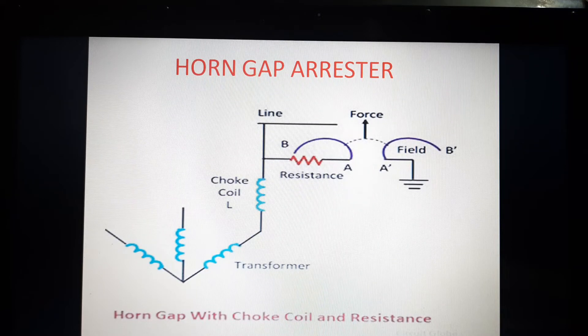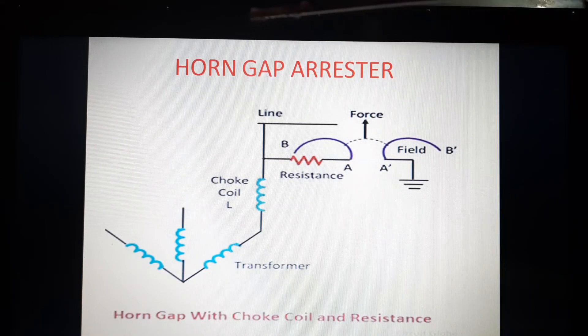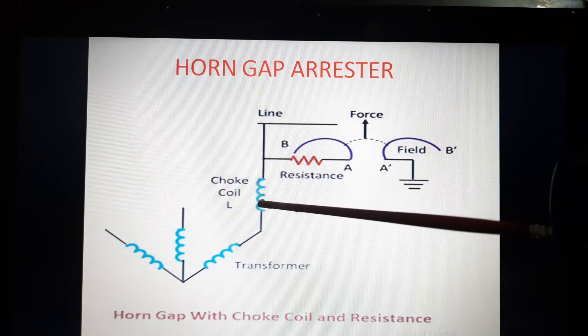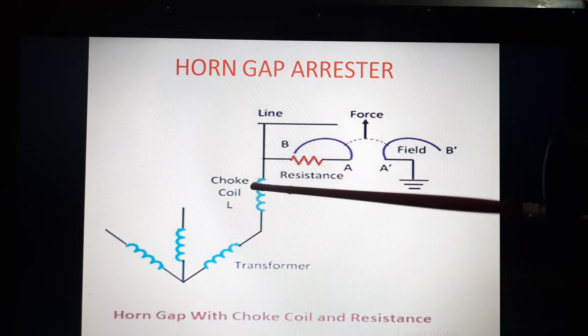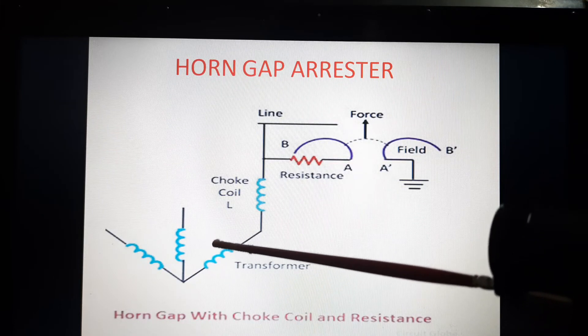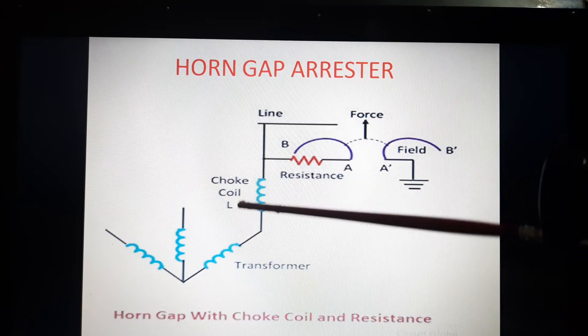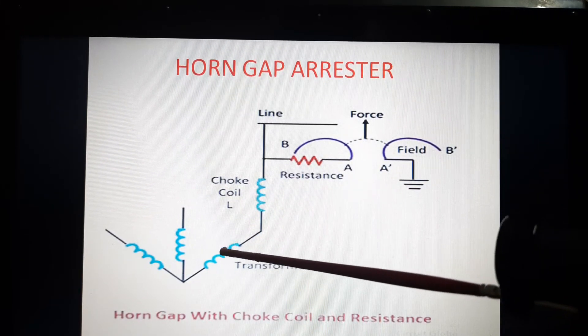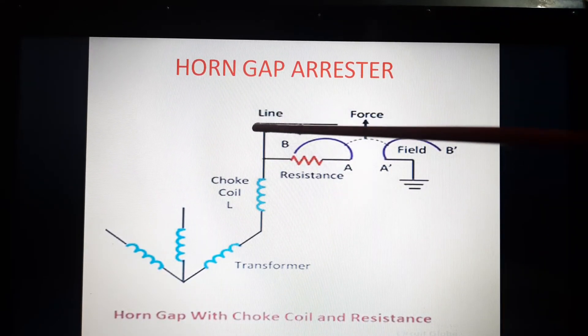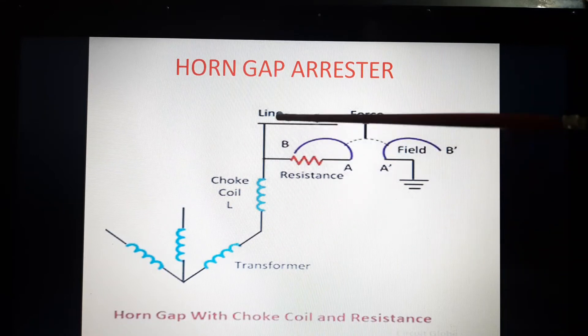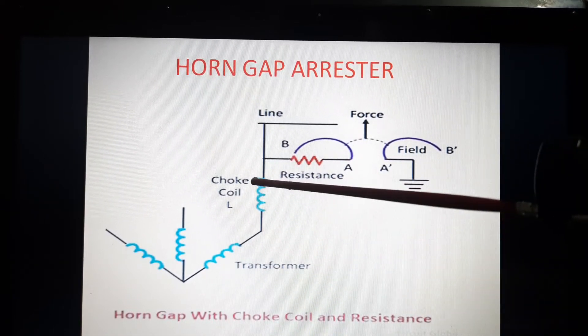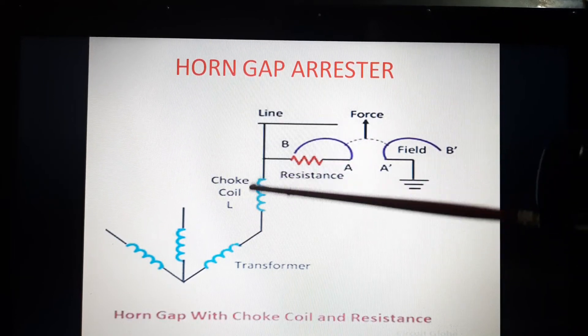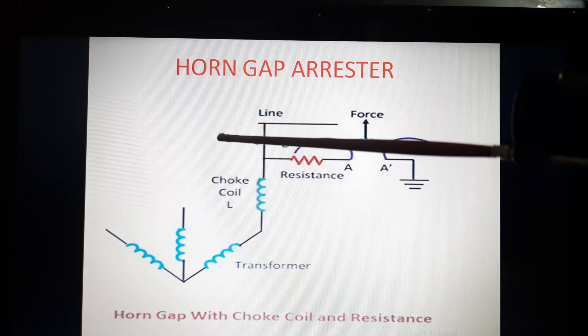During normal conditions, the line voltage goes into the choke coil, which offers very low reactance and allows it to pass through to the equipment. But when there is a high voltage surge condition, the choke coil offers high reactance due to the high frequency of the surge and does not allow the high voltage to pass through the equipment.